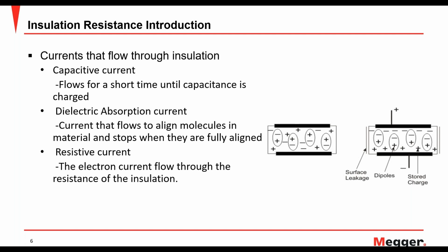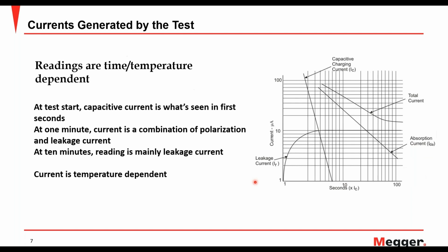Firstly, your capacitive current is only flowing for a short time until your object under test is charged. So that's your first component of the picture. That's your capacitive current. Second is your absorption current. That is the amount of current that is used to align all the dipoles in the same direction. As you see in the diagram right here, turn on my laser pointer. Right here, you see that all the dipoles are aligned in a single direction. So the amount of current that is used to do that is your absorption current. And lastly, you have your leakage current. That is whatever is leaking to ground or any other object nearby.